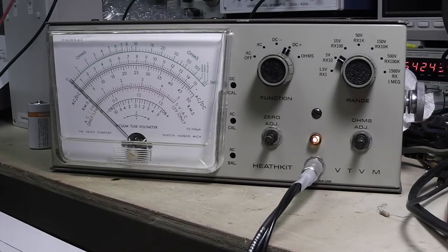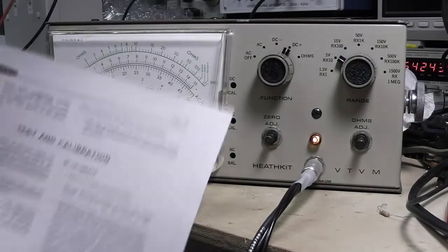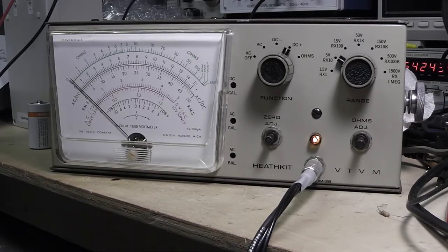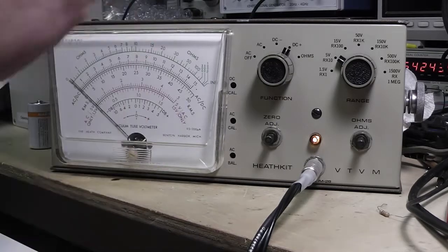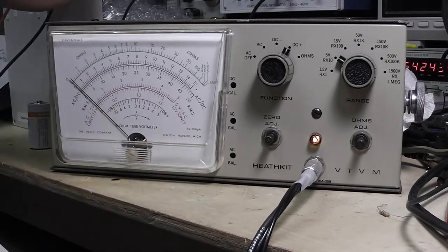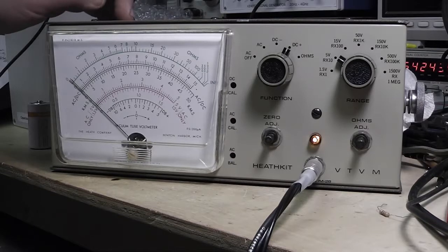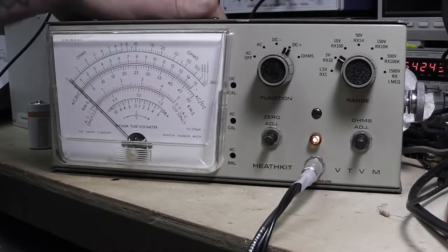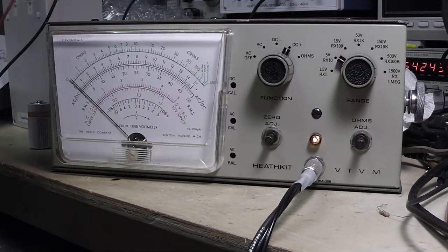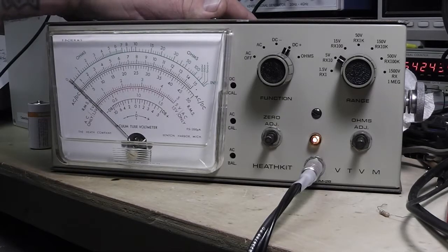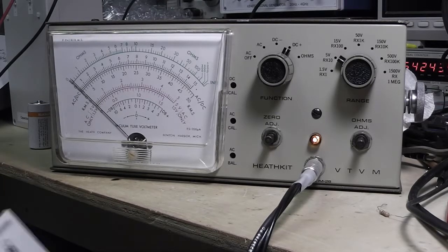I'm going to read it over here to the side. I've printed out the testing and calibration procedure for this particular model. We're going to do it a little bit differently than what it says, because there's one part where it talks about using the battery, putting the battery back in, and then taking the probe and sticking it inside, where the AC line comes in. But there's no need to do that, and I like it put together with the case on and warmed up, so it stays lined up better. And with modern equipment these days, I've got a power supply over here I can set for exactly 1.5 volts. I'll check it with another meter to make sure it's exactly 1.5 volts when we get to that place in the procedure, and set all that.